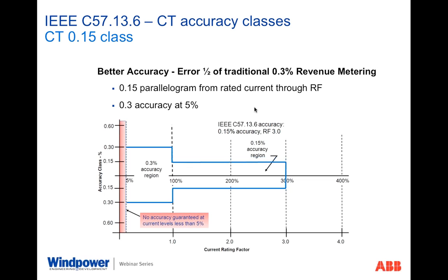So with this introduction of the 0.15 class, IEEE formalized what that meant. And that was an important target because when everybody is using standardized specifications, we all know what the expectations of the other parties are. So in this application, going to a 0.15 meant reducing the error by 1/2 over the 0.3 class. So from 100% of rated current to a rating factor value, shown here as 3.0, that device is in the 0.15 accuracy best range.